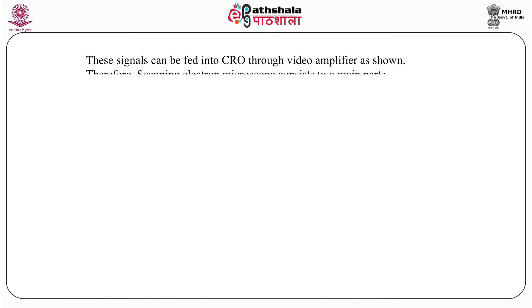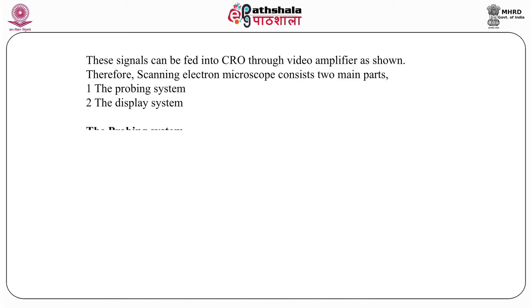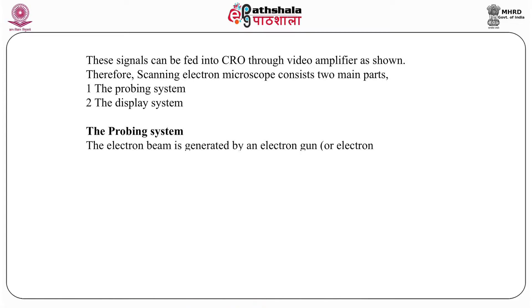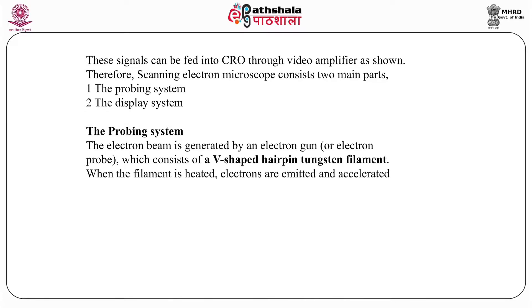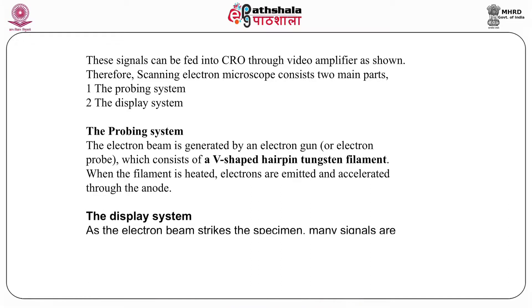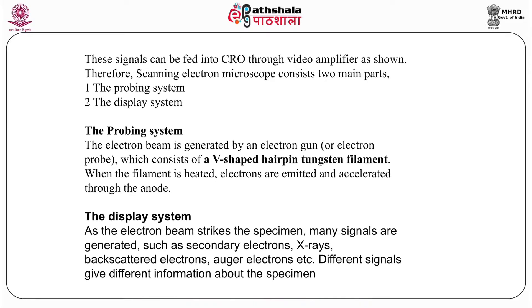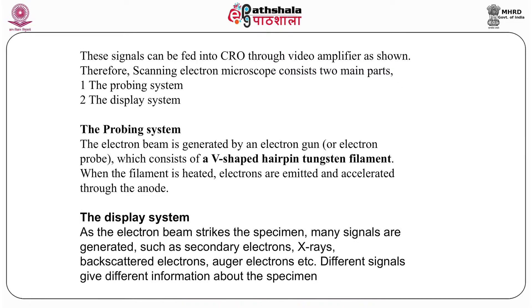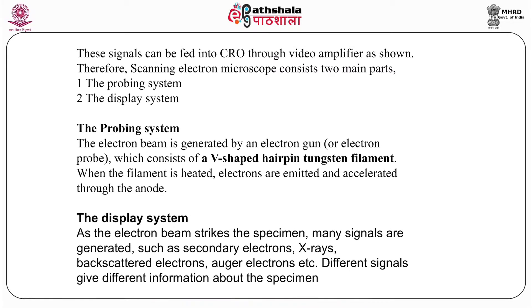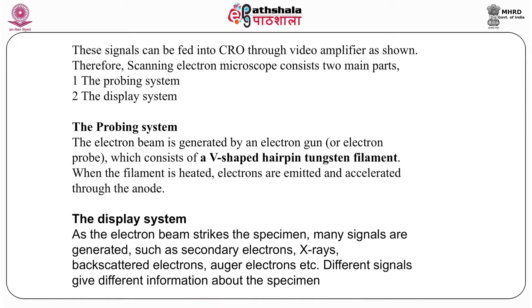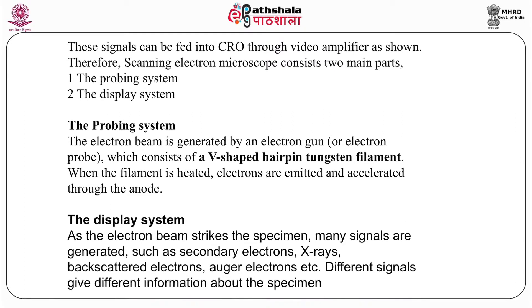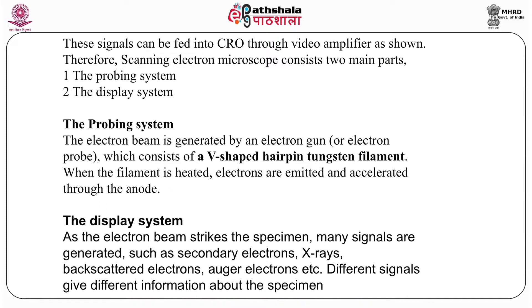In SEM, the signals can be fed into a CRO and the image is amplified. There are two basic components: the probing system and the display system. In the probing system, the electron beam is generated by an electron gun consisting of a V-shaped hairpin tungsten filament; this filament is heated so that electrons are emitted and accelerated through the anode. In the display system, after the electrons are generated and hit the specimen, many signals are generated such as secondary electrons, X-rays, and backscattered electrons.